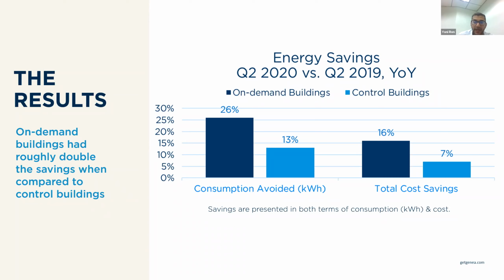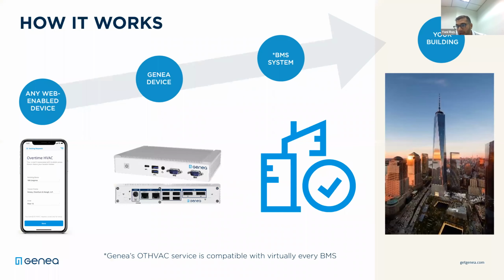A lot of people typically ask us, well, how does it work? It's actually pretty simple. An authorized tenant can request HVAC via any web-enabled device or our website. They enter the date and number of hours they want to receive HVAC. A signal is sent into our device that is connected directly to the building automation system. We override what's called an occupancy point in the building automation system at a higher priority than the building schedule, taking into consideration all the normal functions of the BMS and the mechanical setup, including minimum load requirements to ensure the equipment is running properly.